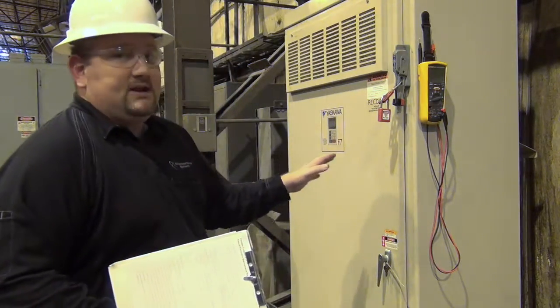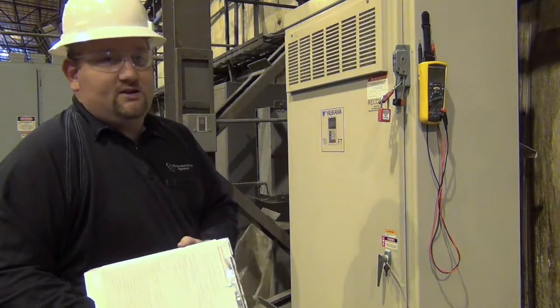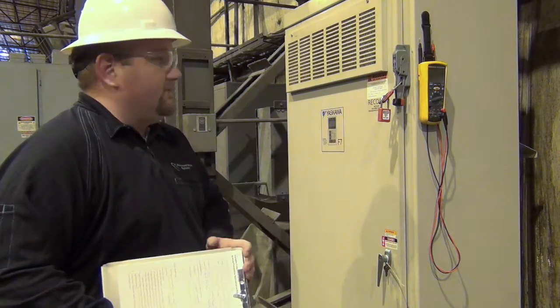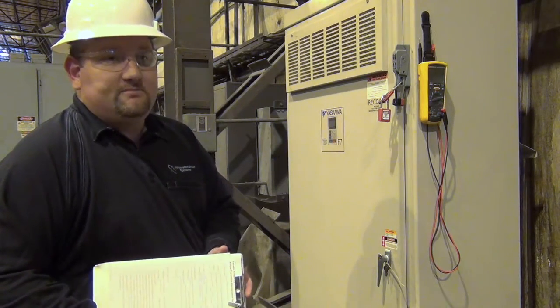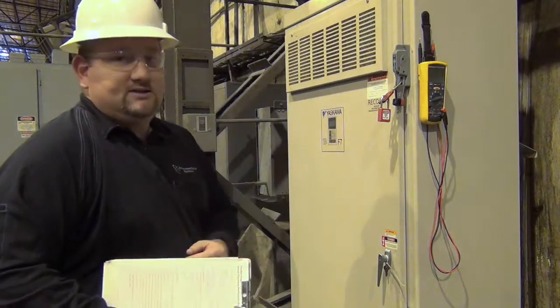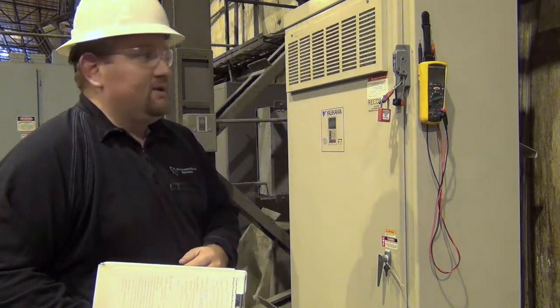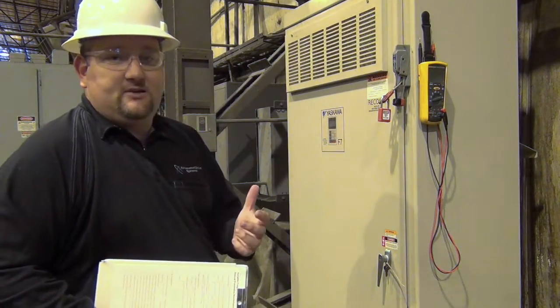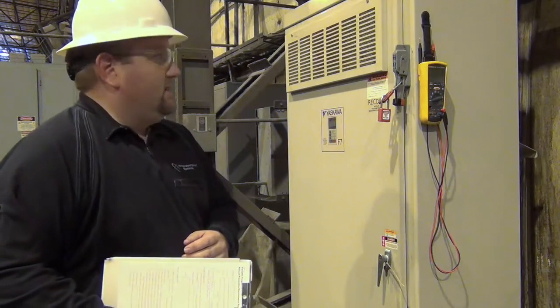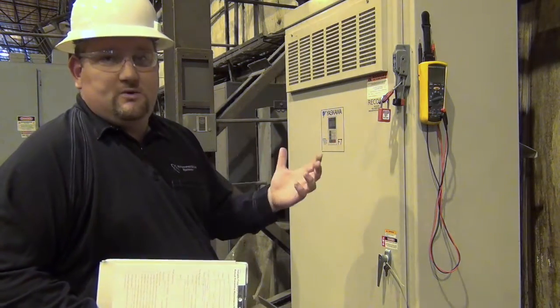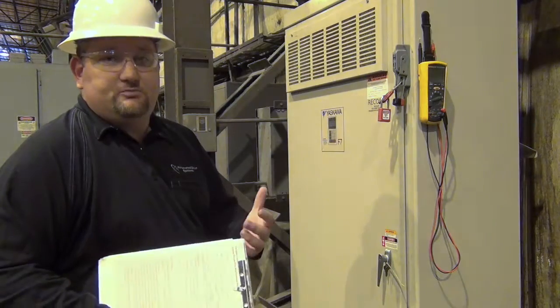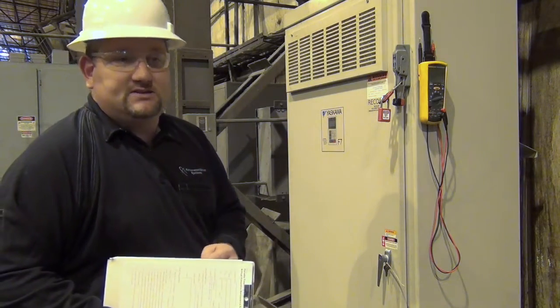So the drive we're working on today is a Yaskawa F7 series. This drive was installed about 6 years ago. It is a pretty good example of a standard drive that's been in industry. Not a lot of detailed maintenance has been performed on it. And like I said, we're going to go through and see what we can see and show you guys how you actually should properly maintain the drives that are in your facility.